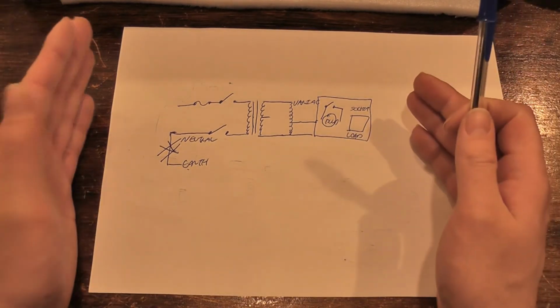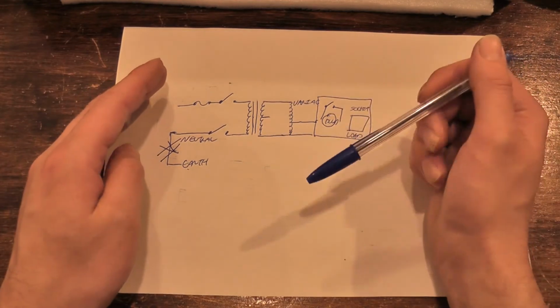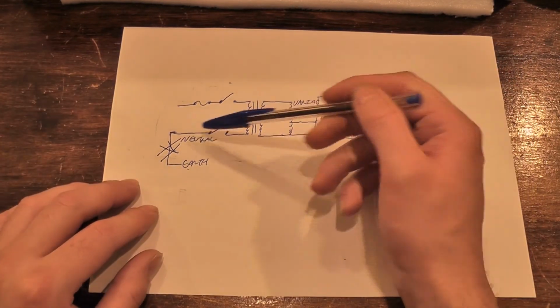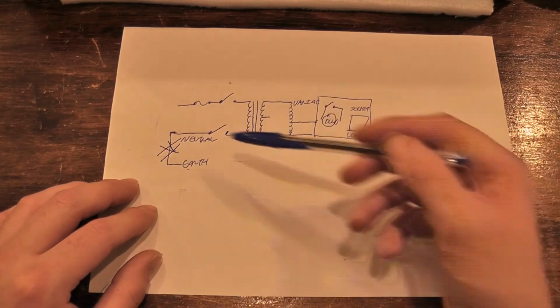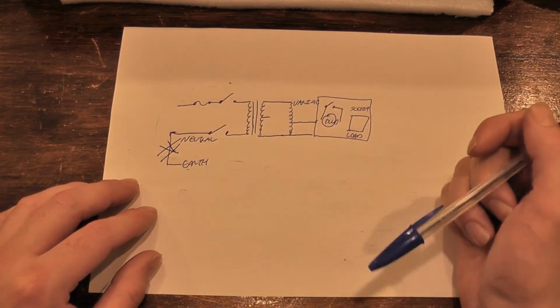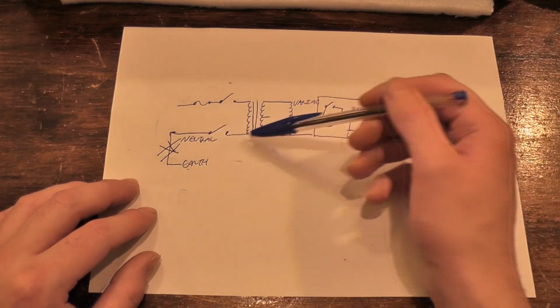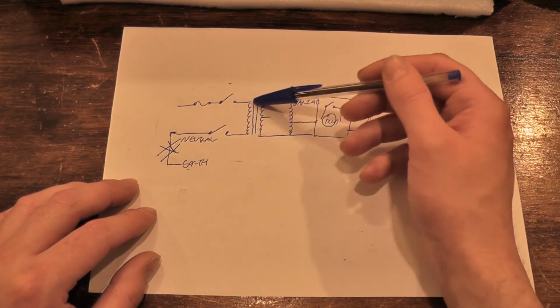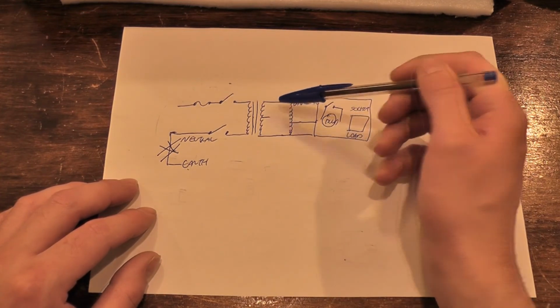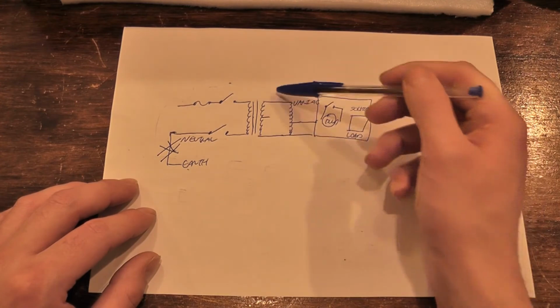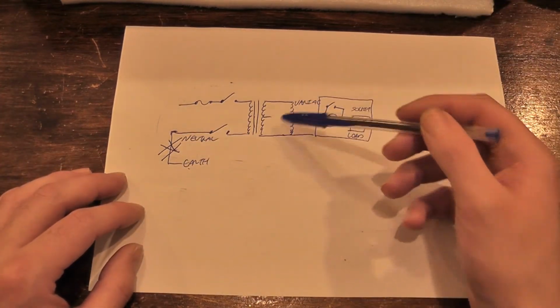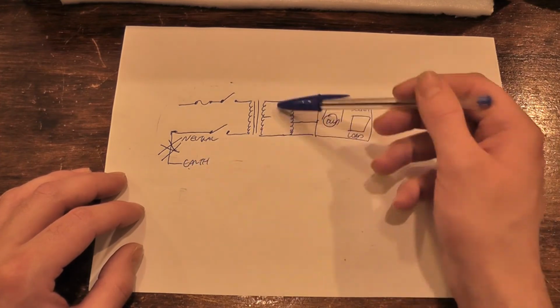It'd be a very robust piece of test equipment. Because it's got the isolation transformer, it breaks - especially in England, where we have the PME system where earth and neutral are tied together - it breaks that connection. So if you happen to touch something live, instead of it now being at mains potential against earth via you, it's open circuit.